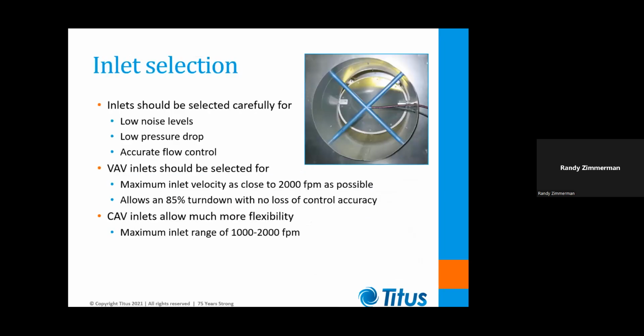Now let's take a look at sizing and selecting. I've got some golden rules that I use for selecting box inlets. And the first thing is when I'm doing a VAV inlet, I try to size the inlet for as close to 2,000 feet per minute inlet velocity. Because I know if I do that, it's going to prevent me from oversizing the inlet, oversizing my ductwork. And it's also going to give me a very comfortable VAV turn down of 85% without losing my accuracy on my flow control. Now, if I'm doing a constant volume terminal, I've got a much wider selection range of 1,000 to 2,000 feet per minute because there's no VAV turn down to consider.